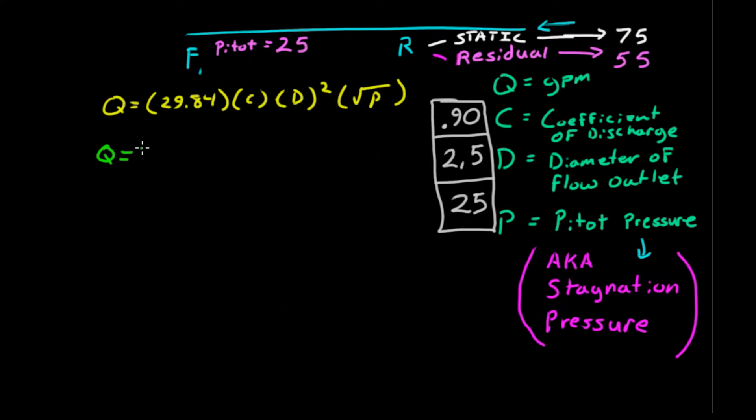29.84 is a constant. Coefficient of discharge would be 0.9, and then 2.5 squared is 6.25. And pitot pressure of 25, the square root of 25 is 5. And just as a side note, pitot pressure is also known as stagnation pressure, not static pressure. Totally different pressure.